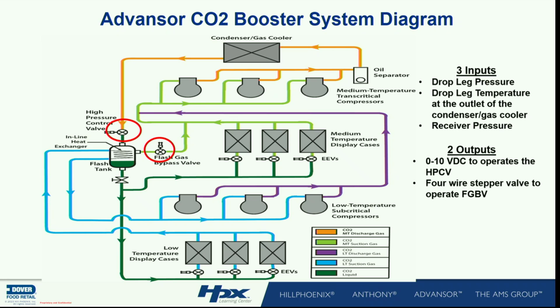It doesn't matter who you're using, we have these inputs and outputs. Typically, if I'm using a high pressure ICMT valve, I'll have a 0 to 10 volt signal that drives it based on COP. If I'm using a CCMT valve, then I have to have a valve driver to control that. We'll talk about both.